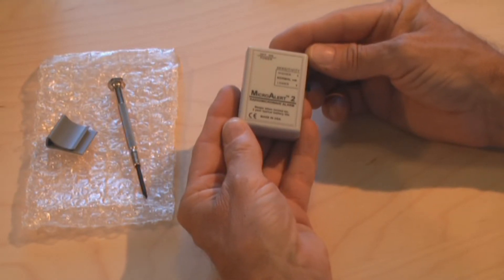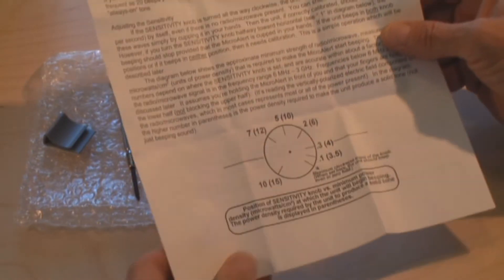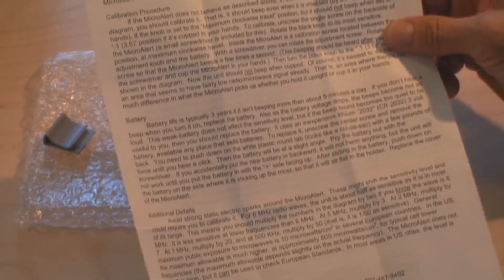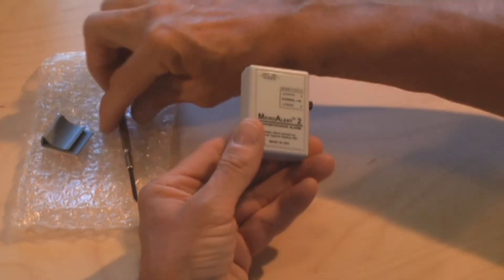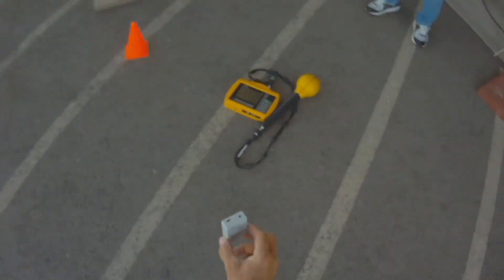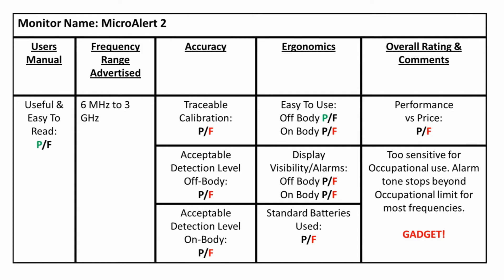This is the MicroAlert 2, the smallest monitor that we tested. I ordered it online for about $100. According to the manual, the device has a very broad frequency range from 6 MHz to 3 GHz. The advertised sensitivity is up to 10 microwatts per square centimeter. A calibration certificate was not included, and it uses a CR2032 battery. This monitor reacted to every frequency we tested. Unfortunately, it proved to be too sensitive for use as a piece of personal protective equipment. It failed every one of our accuracy tests, and in my opinion, this is just an overpriced gadget.